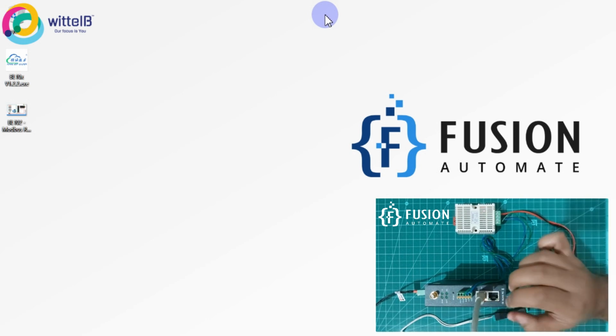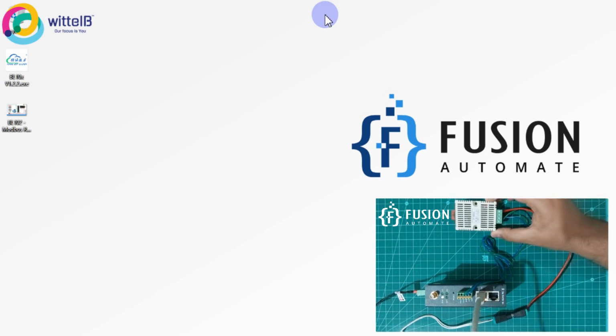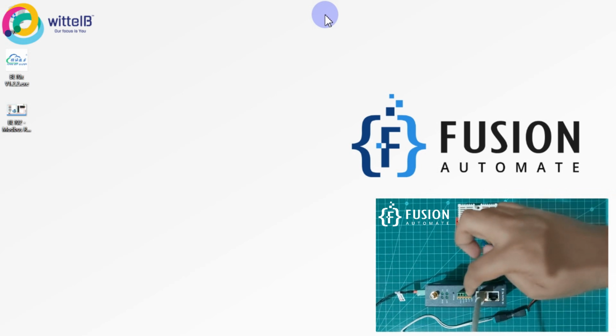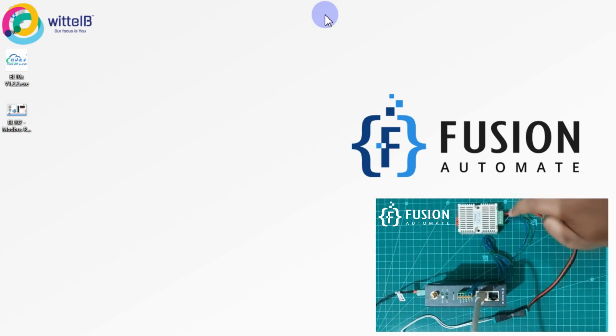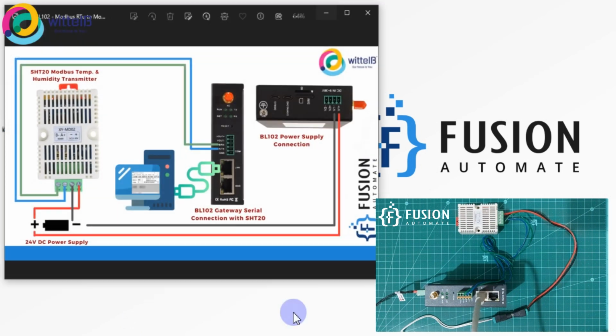Okay, so now in today's video we will use this gateway and we are going to see one functionality of this gateway. As you can see here, I have this SHT20 temperature and humidity transmitter, and this transmitter is providing data over the Modbus serial protocol. So I have connected this transmitter to this gateway, as you can see, the blue and green wire here, and it is also connected with this gateway. Now with this gateway, what we are going to do is we will convert the Modbus serial data into Modbus TCP data. Now let's see the diagram which we have followed for connection.